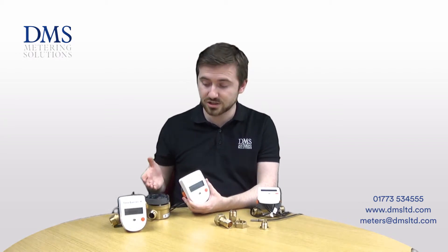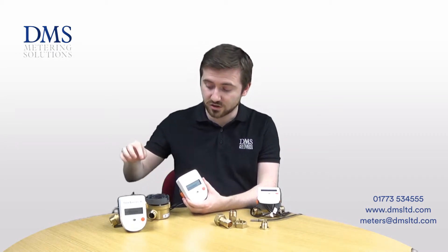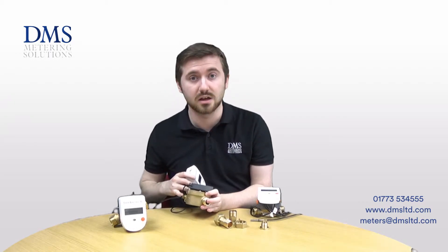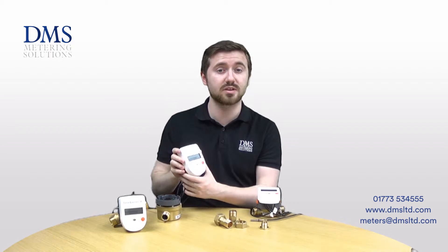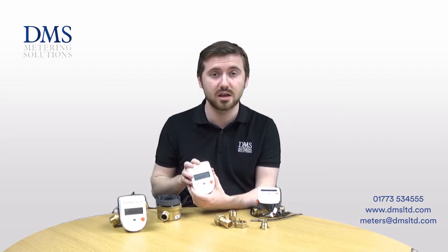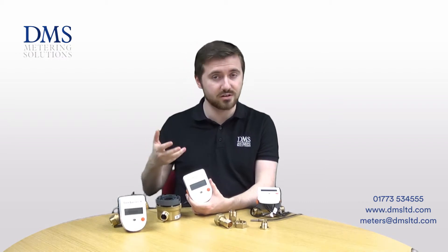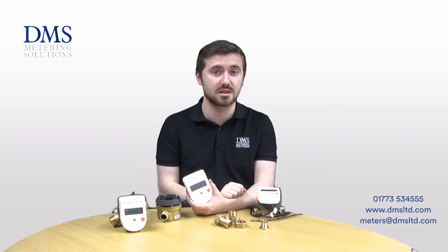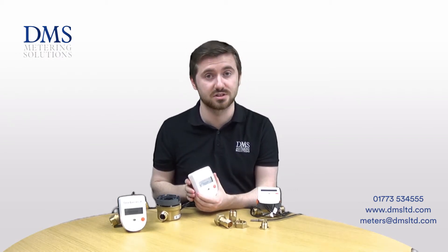This meter range is a compact design, which is obviously part of the smaller sizes as well, but based on this you actually get a temperature sensor mounted in the meter body. That's predominantly the return temperature sensor, but of course the meters can be recalibrated for flow as required, whereby the temperature sensors will be swapped around. This design means that there is a much smaller installation cost for installers, as they don't need to mount a second socket for the return or alternative temperature sensor.